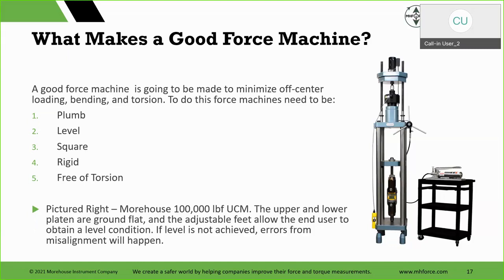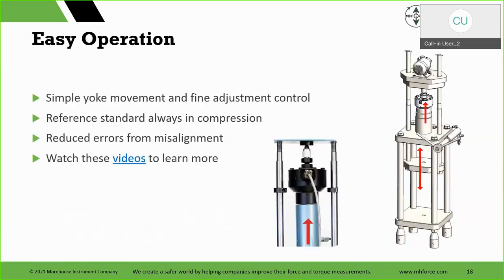Adjustable feet allow the end user to obtain level condition. If level is not achieved, this is the big disclaimer here, you can level the machine, but if you decide not to do it, you're gonna have high errors. That's with any force machine. Easy operation, simple yoke movement and fine adjust control. Reference standard always in compression, reduce errors from misalignment. And then we have all these videos there.